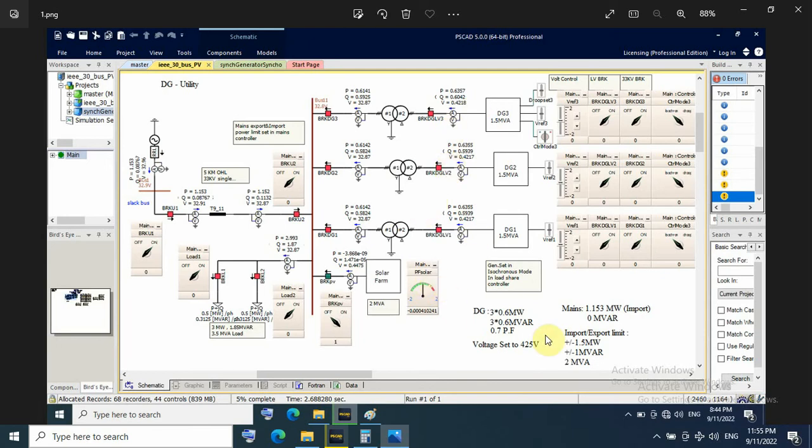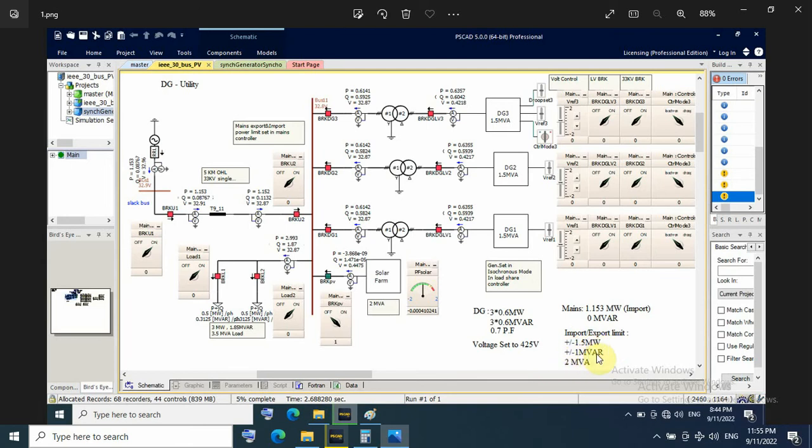This means 1.153 megawatt imported power, active power and 0 megavar. That means at unity power factor. And the import and export limit from utility about plus minus 1.5 megawatt and plus minus 1 megavar or 2 MVA. That's about 1.8 to 2 MVA. This import export limit.